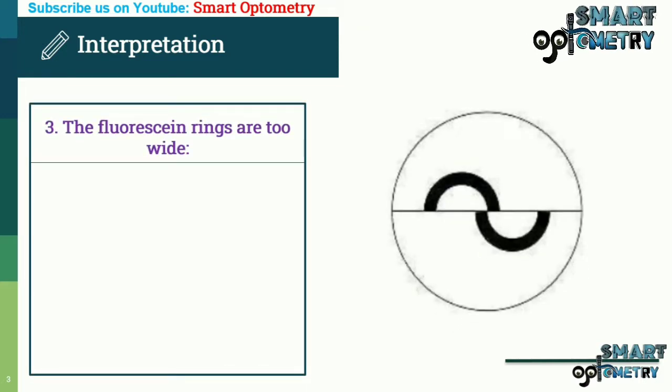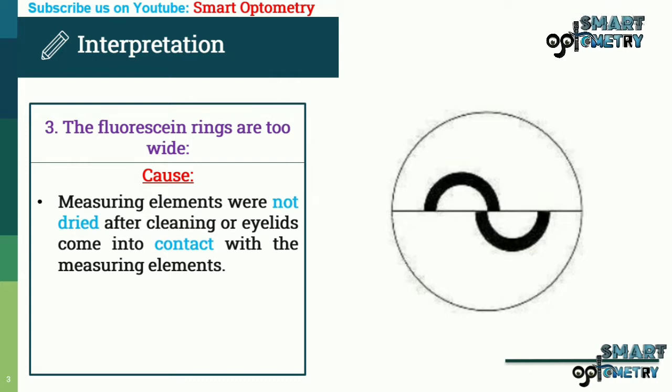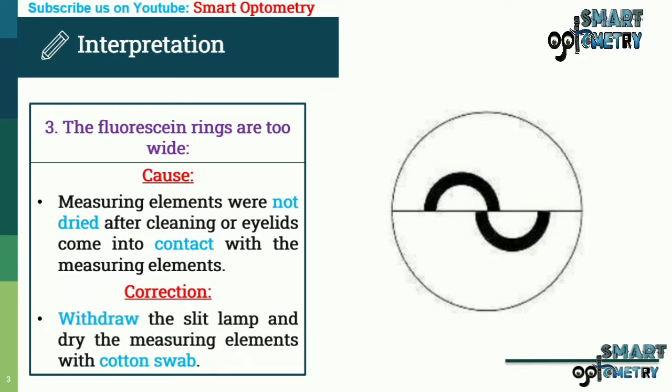Fluorescein rings are too wide. This is because the measuring elements were not dried after cleaning, or eyelids came into contact with the measuring elements. The correction is to withdraw the slit lamp and dry the measuring elements with a cotton swab.